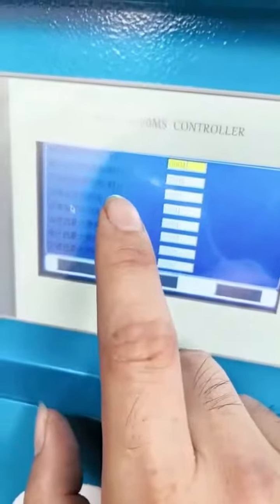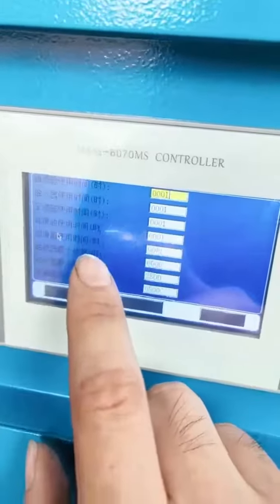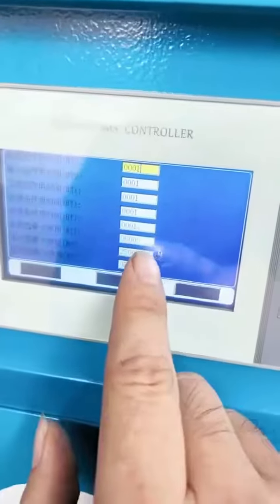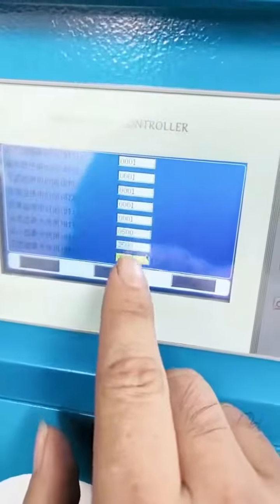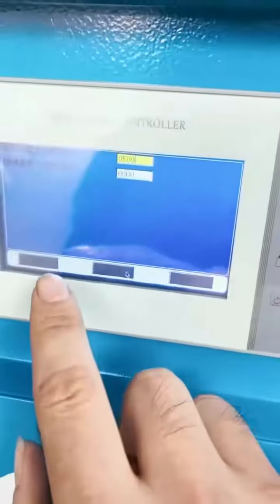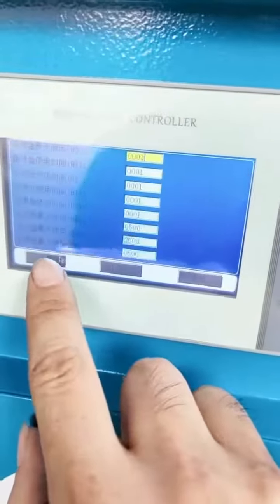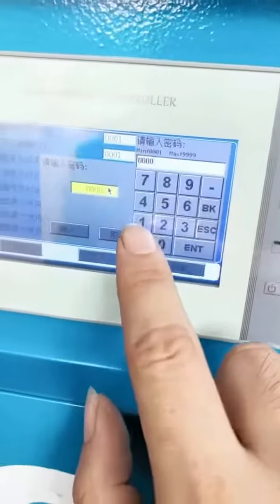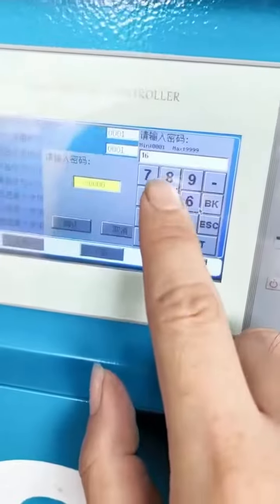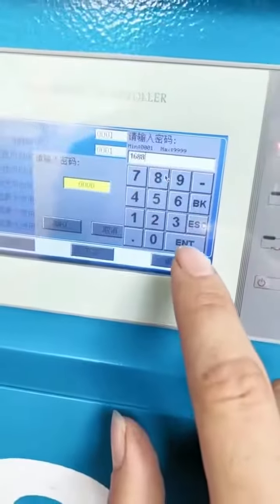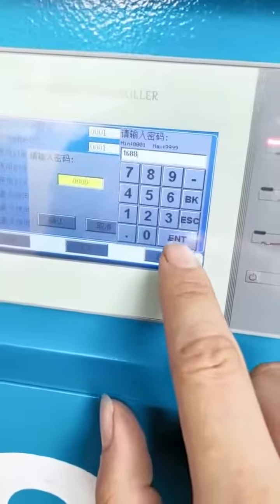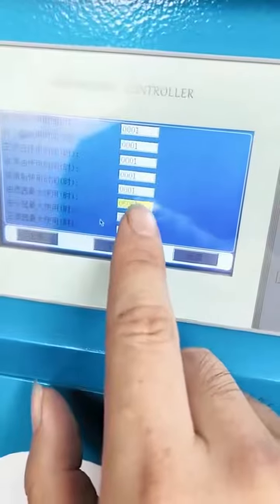Click max use time of oil filter, max use time of oil separator, max use time of oil and air filter, max use time of lubricating oil, and max use time of grease. Enter the password 1688 to confirm, and adjust all times to 2,500.